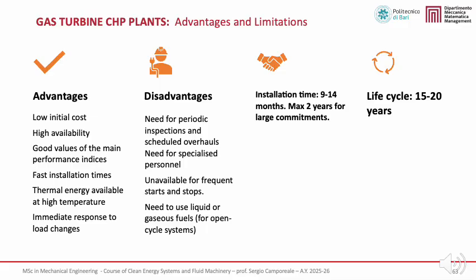On the other hand, gas turbine CHP plants require periodic inspections and scheduled overhauls due to operation under high thermal and mechanical stresses, and they need specialized personnel for correct operation. They are also less suitable for very frequent start-stop operation and generally require liquid or gaseous fuels in open cycle configurations. Typical installation times range from 9 to 14 months, while the expected service life is about 15 to 20 years.